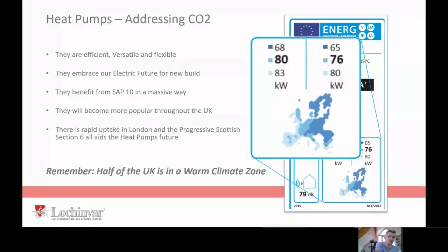When you look at an air source heat pump, water source heat pump, any type of heat pump, there will be a SCOP figure given. You've got COP, which is coefficient of performance at a specific point in time. Then you've got SCOP, which is seasonal coefficient of performance, because its efficiency is going to be dictated by the climate it's working in.